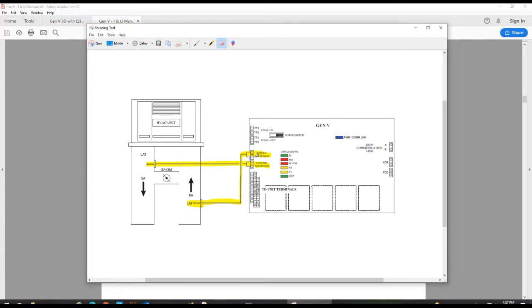A couple other things to note on the Gen V controller. We do have several status lights. Your blue light here is your power light, and you have status lights for the operation or output the controller is making. A green light would mean fan is running. 2 red lights would be an indicator of first and second stage heat. 2 yellow or amber lights would be indication of first and second stage cool.